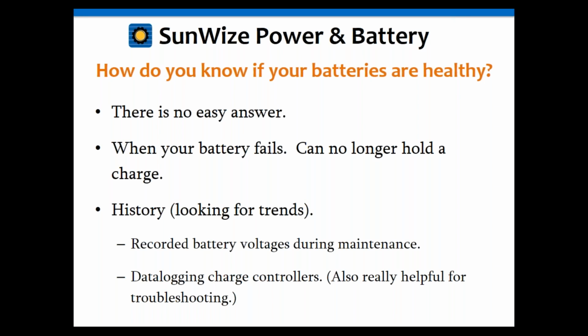But again, unfortunately, at that point, that's when your battery's pretty much completely failed, and your system may have failed because of it. So unfortunately, that's not what people want to hear, but if it comes to that point, your batteries are already in really bad shape, and your system's probably failing because of it. So hopefully you can try to find it before it happens, but again, this is not an easy thing to do. One of the best ways to look for it before it happens is to look at the history, look for trending. And this can be done by recording your battery voltages.